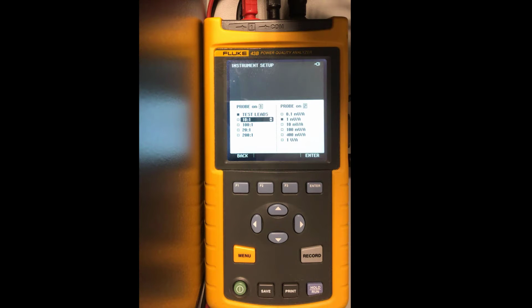So essentially with this setting, one way to determine if you've forgotten to do this is if you see factors of voltage in a circuit where you only have, say, 50 volts AC, and you end up seeing it showing up as 500 volts AC, or things of that nature. It's telling you that something's wrong with your calibration. So in this case, I'm 1-to-1, so I want to make sure it's that setting.